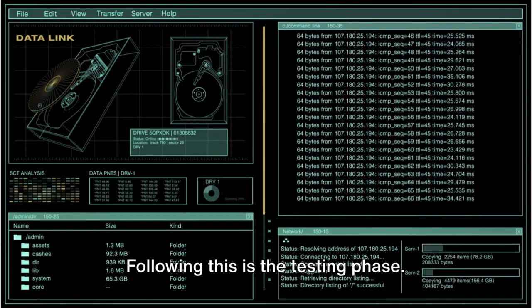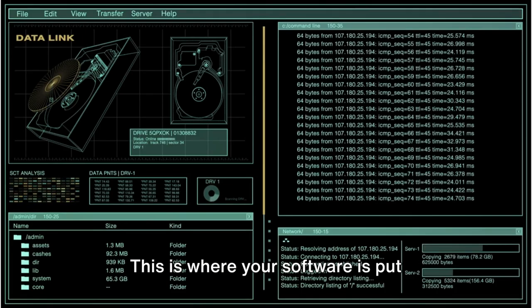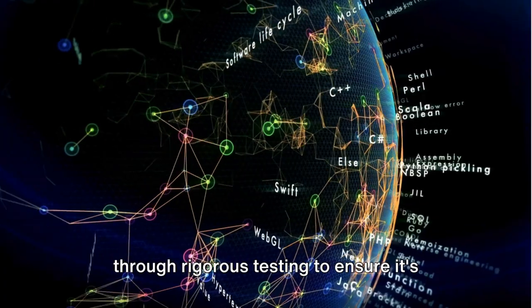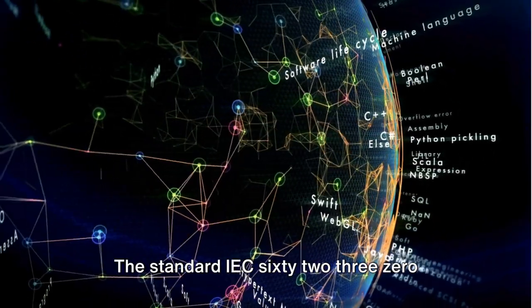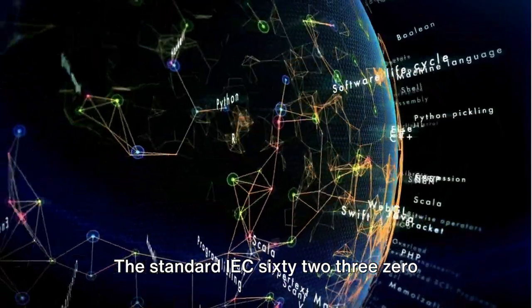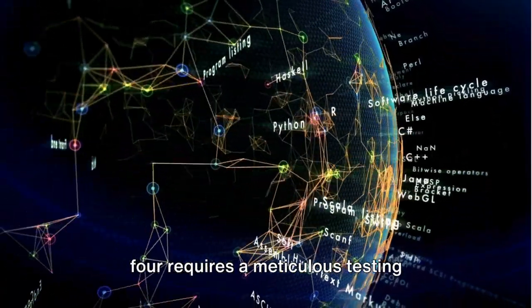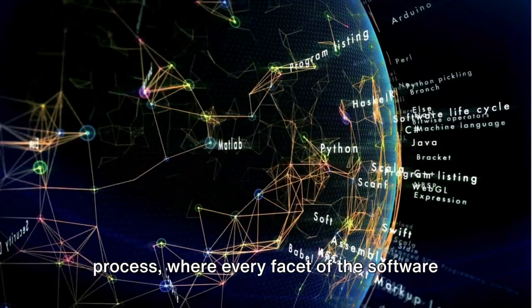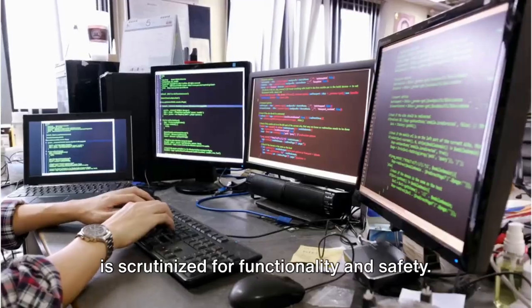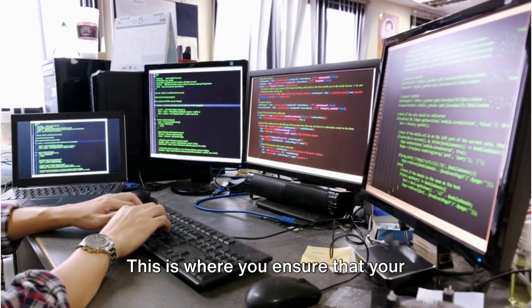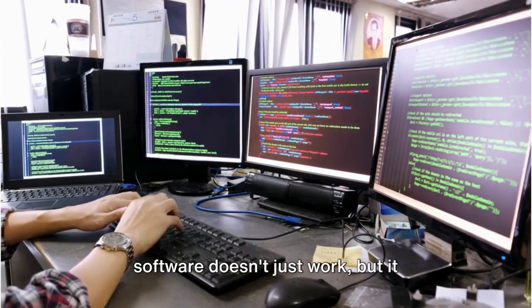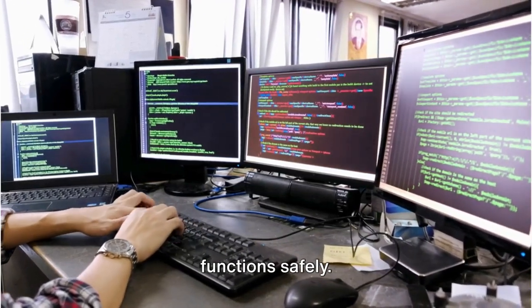Following this is the testing phase. This is where your software is put through rigorous testing to ensure it's fit for purpose. The standard IEC 62304 requires a meticulous testing process, where every facet of the software is scrutinized for functionality and safety. This is where you ensure that your software doesn't just work, but functions safely.